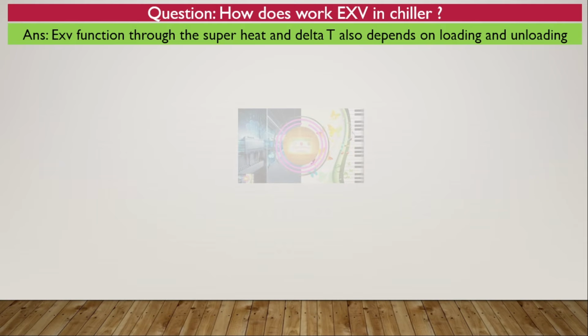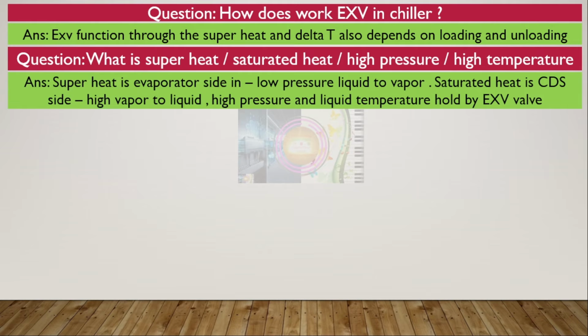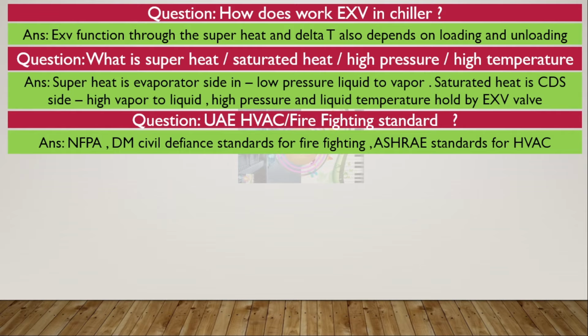Question. How does EXV work in a chiller? EXV functions through the superheat and delta T, and also depends on loading and unloading. What is the superheat? Saturated heat is high pressure, high temperature. Superheat is on the evaporator side, in low pressure liquid to vapor. Saturated heat is on the condenser side, high vapor to liquid. High pressure and the liquid temperature are held by the EXV.